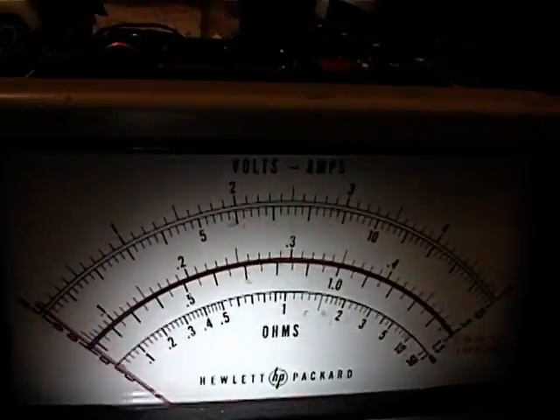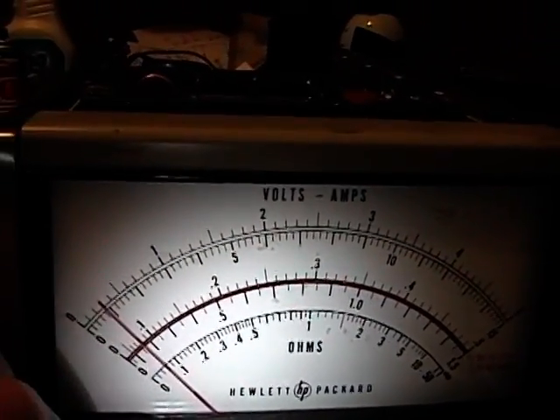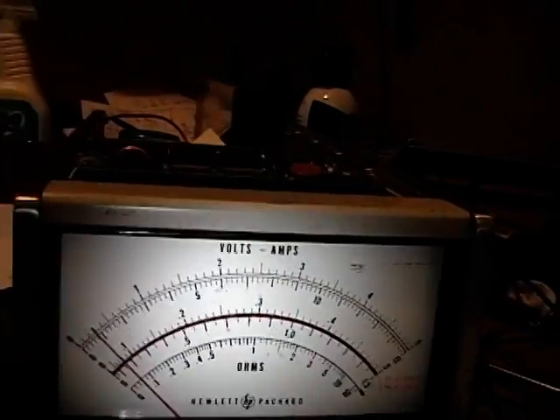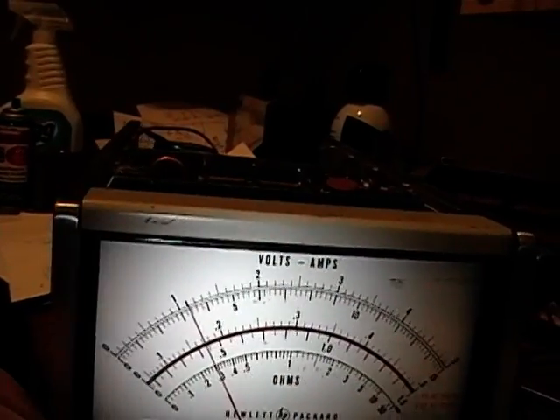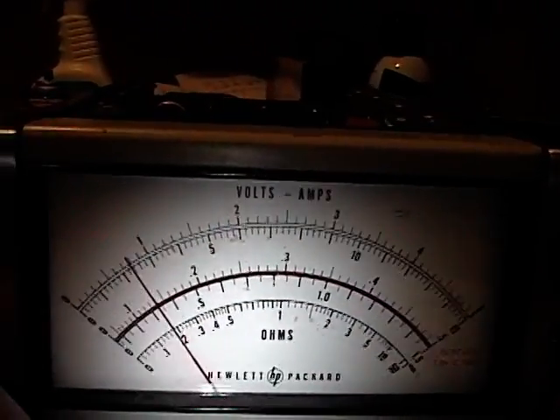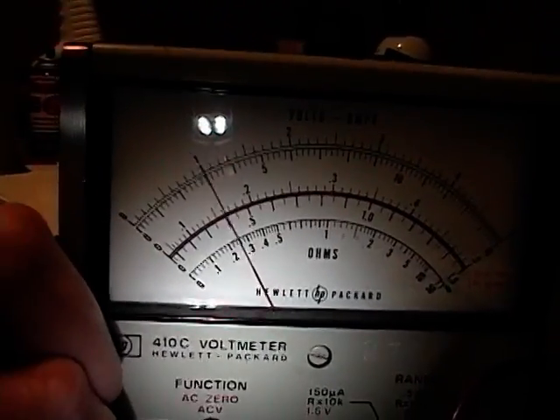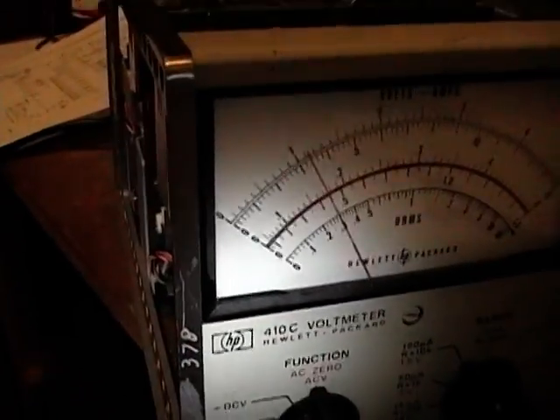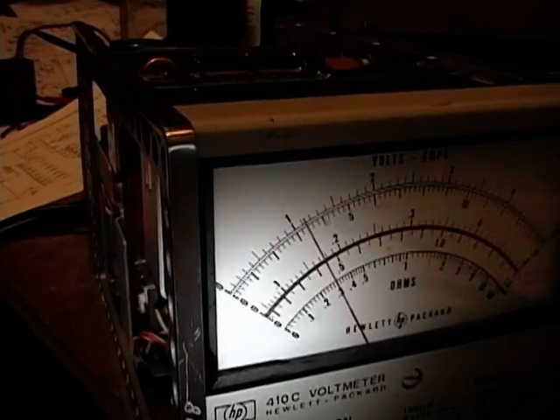And I assume that has to do with the zeroing control, because if that's off, of course, all your readings are going to be off. On the lower range, let's see, 1.5, so it should be about over here instead of way over here. But again, the zeroing control does have an effect. So if I could just get that offset to go over a bit more, I think I'll be all right.